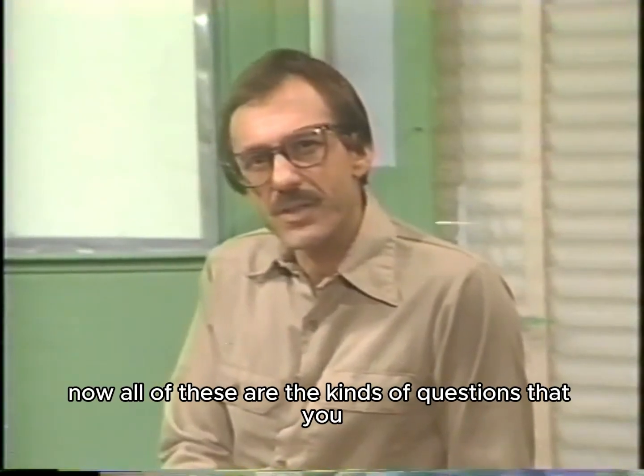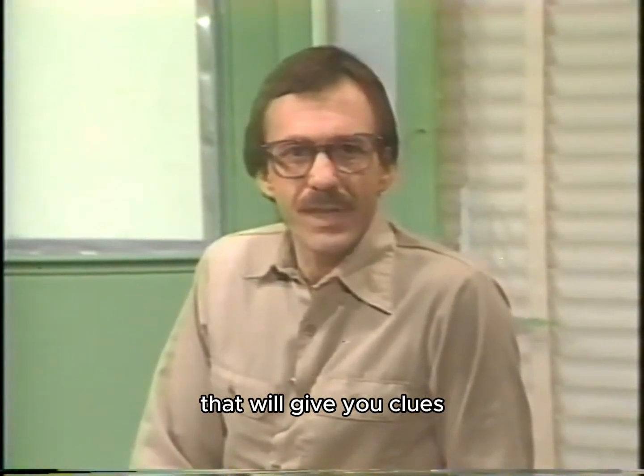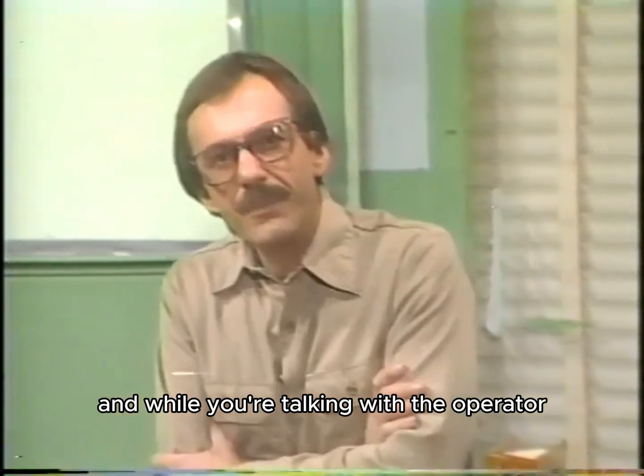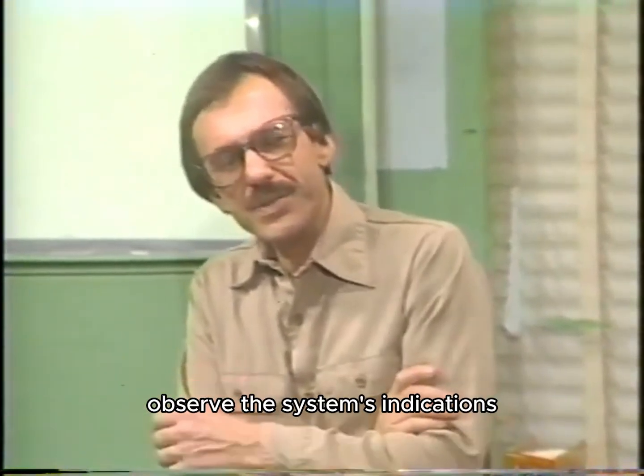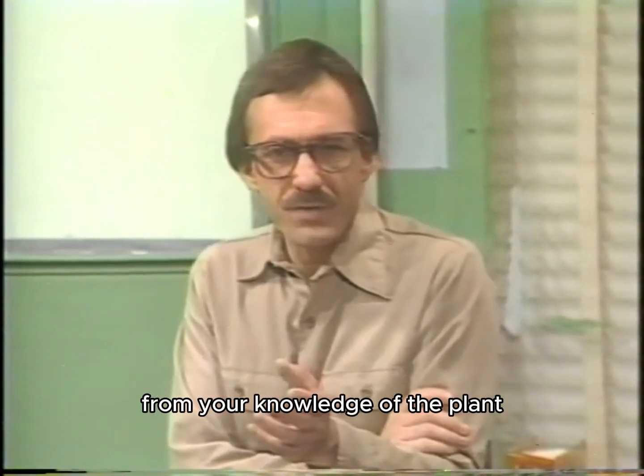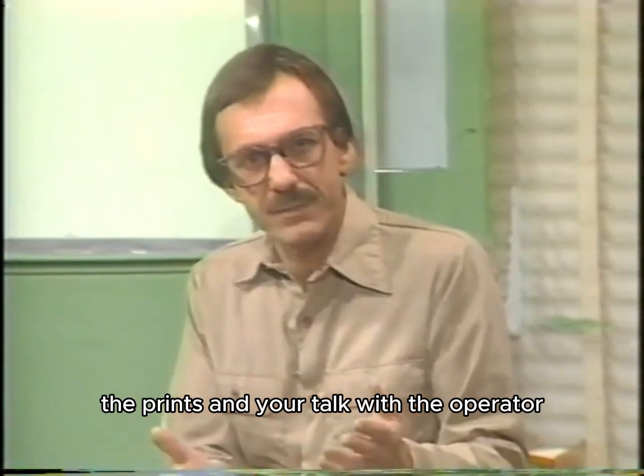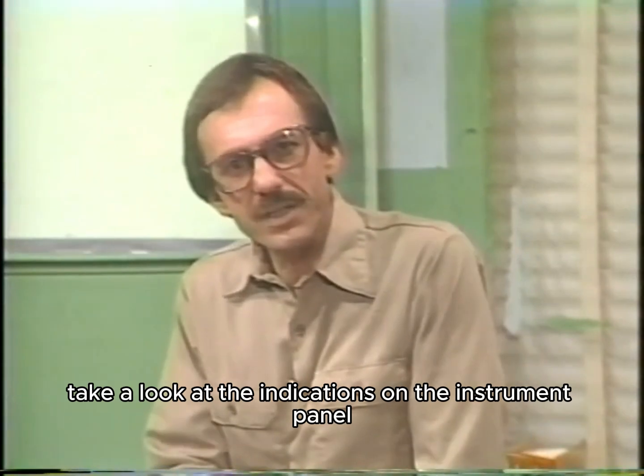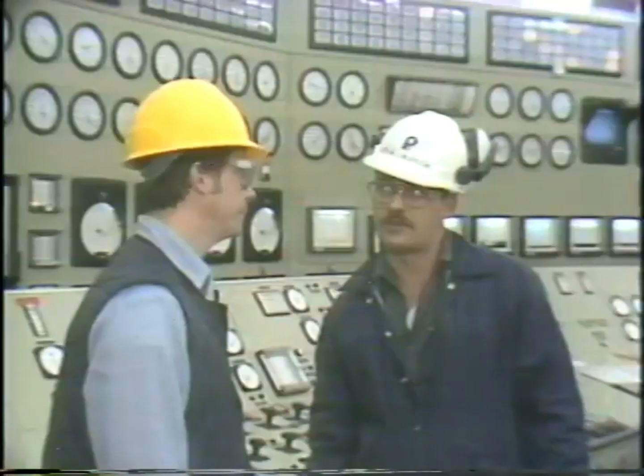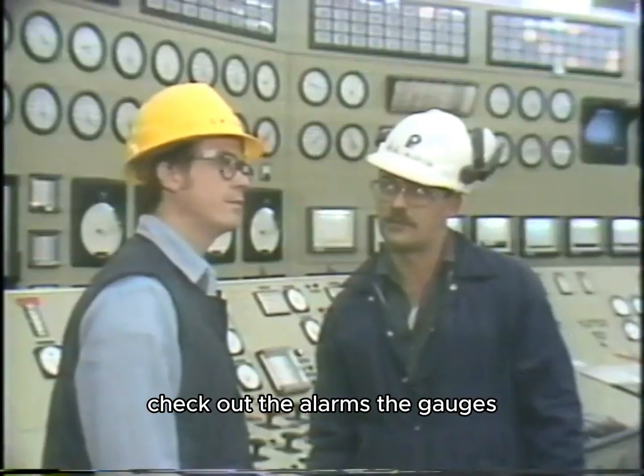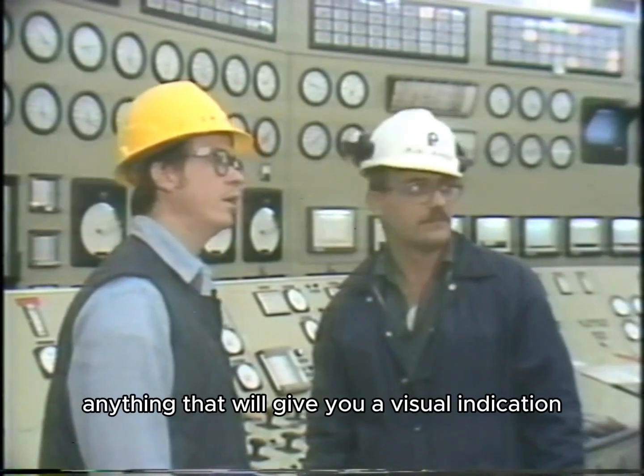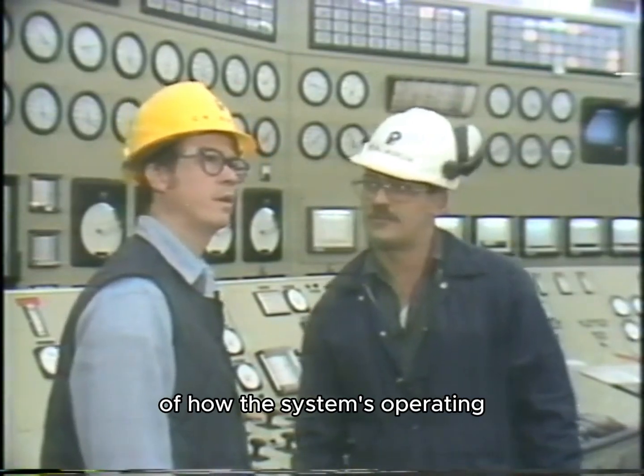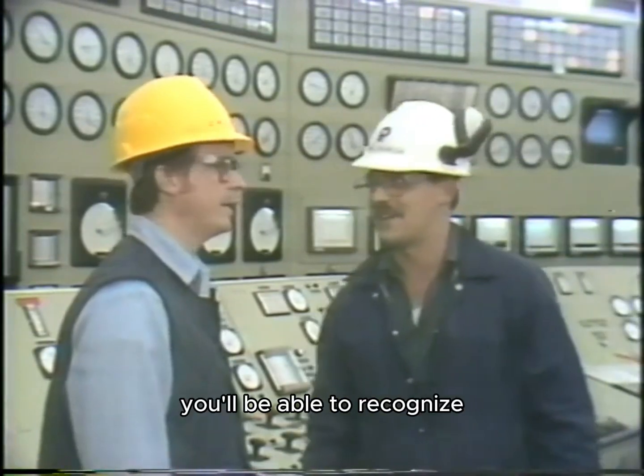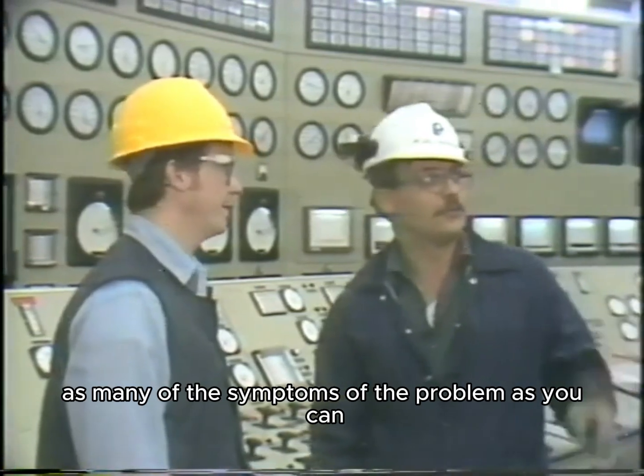Now, all of these are the kinds of questions that you can ask the operator. That will give you clues as to the nature of the problem. And while you're talking with the operator, observe the system's indications. Now, from your knowledge of the plant, the prints, and your talk with the operator, take a look at the indications on the instrument panel. Check out the alarms, the gauges, the recorders, anything that'll give you a visual indication of how the system's operating, so that you'll be able to recognize as many of the symptoms of the problem as you can.